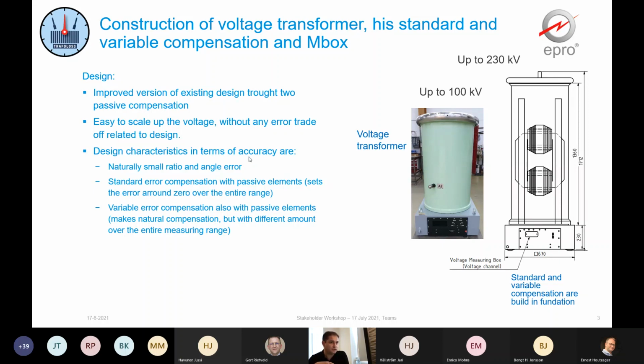Similar to the standard compensation is the variable compensation. The only difference here is that it can and does change its value over the measuring range. So usually, at a lower range where the natural error is higher, you can have more impact on compensation than at a higher range. And this fact, in combination with the standard compensation, can lead to higher accuracy over the entire range and ultimately less uncertainty.